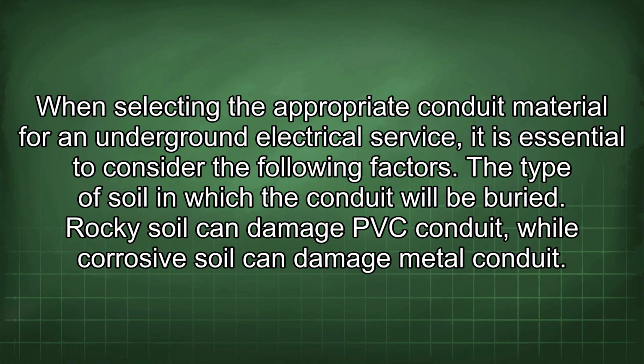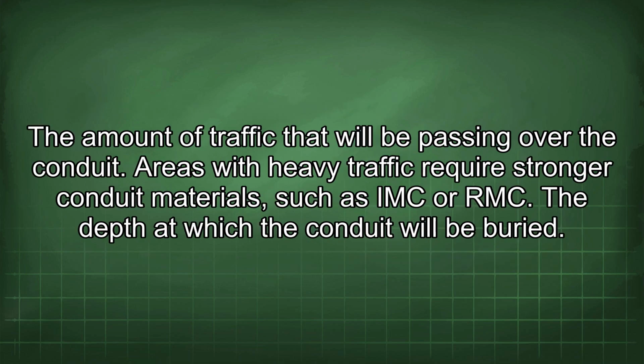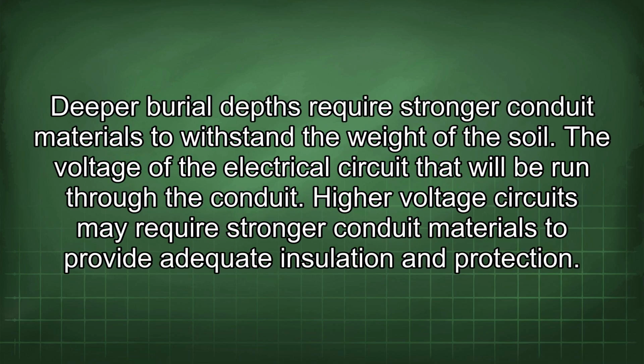When selecting the appropriate conduit material for an underground electrical service, it is essential to consider the following factors. The type of soil in which the conduit will be buried. Rocky soil can damage PVC conduit, while corrosive soil can damage metal conduit. The amount of traffic that will be passing over the conduit. Areas with heavy traffic require stronger conduit materials, such as IMC or RMC. The depth at which the conduit will be buried. Deeper burial depths require stronger conduit materials to withstand the weight of the soil.